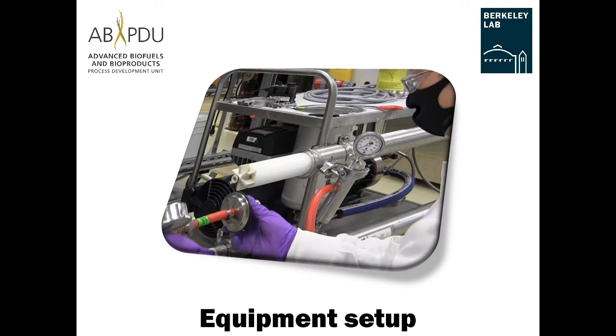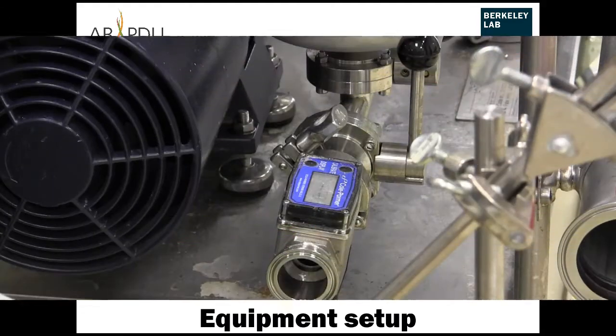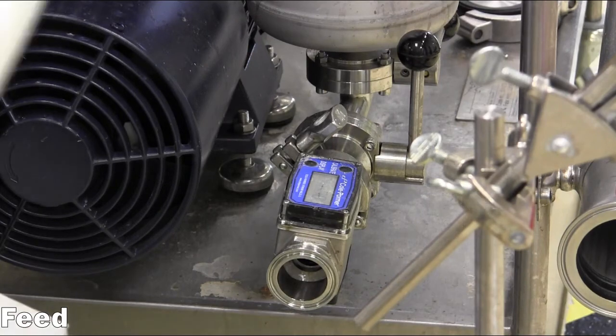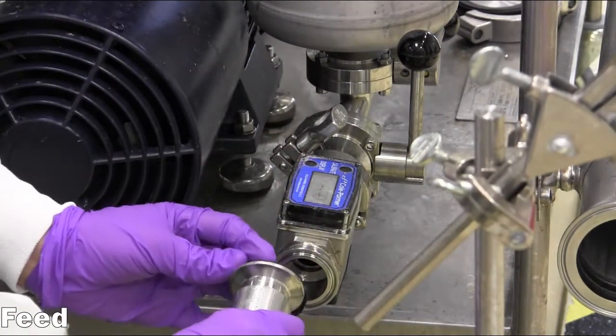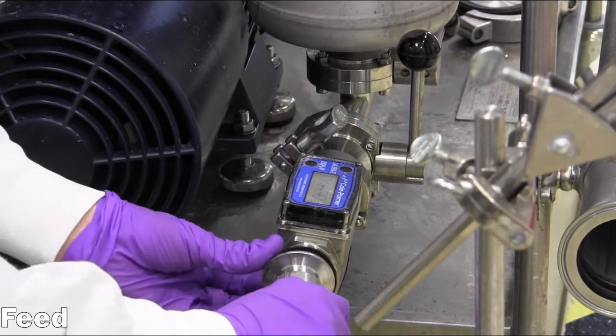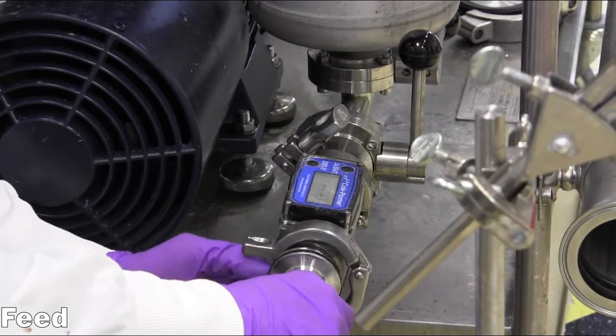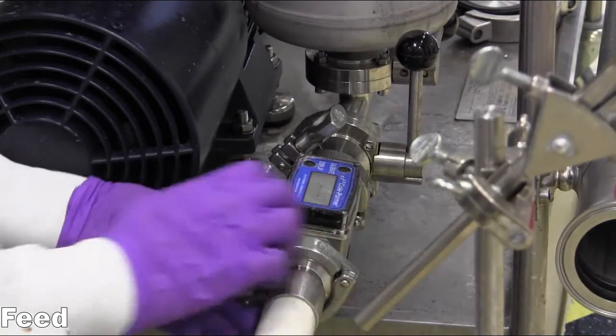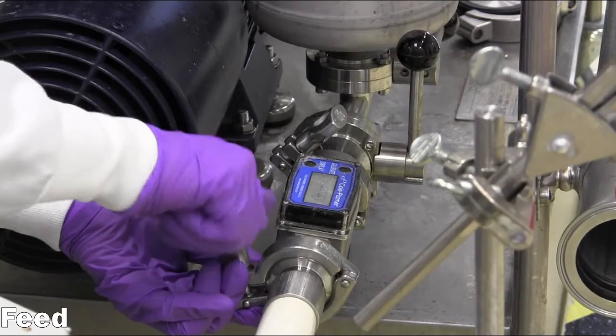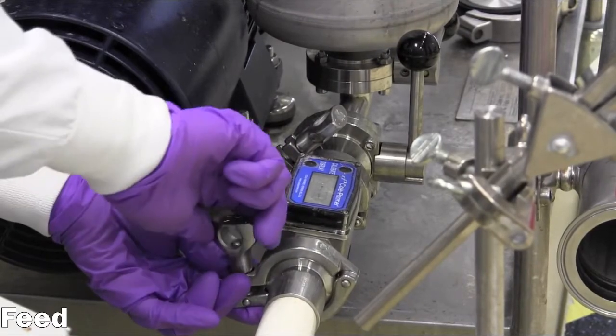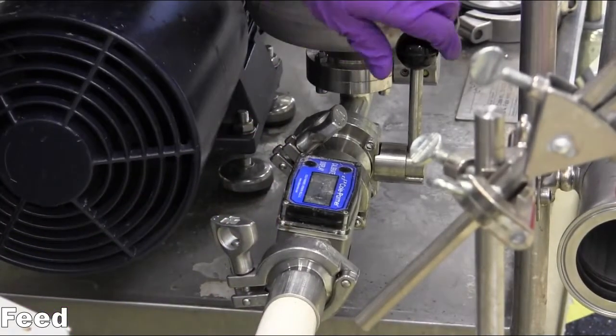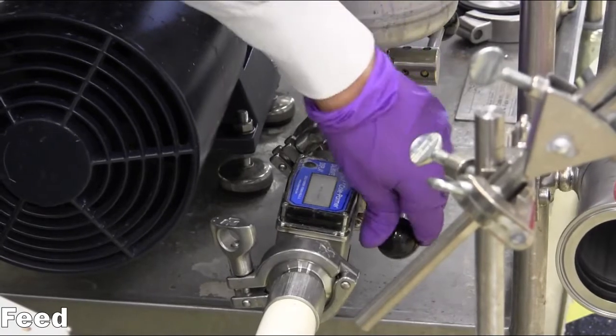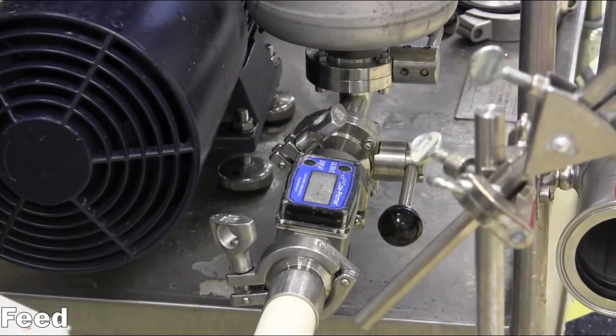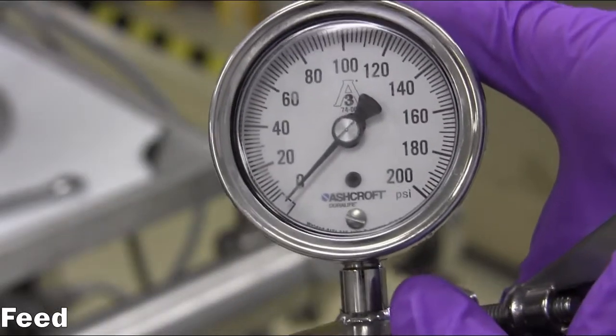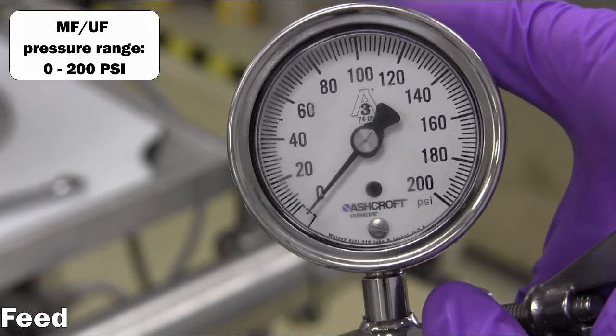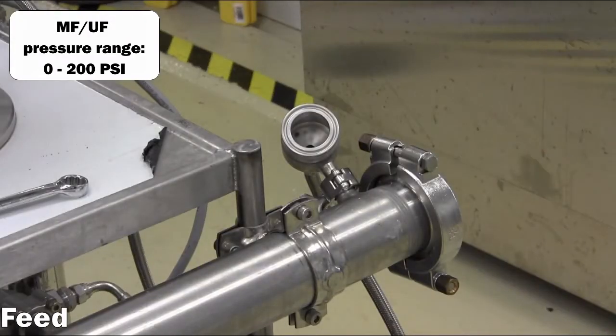Equipment setup. A hose is connected to the digital flow meter attached to the feed inlet port below the small feed tank via a sanitary tri-clamp connection. Then the three-way valve is switched to allow flow from the feed hose. Connect a pressure gauge to the inlet manifold to allow the inlet pressure to be monitored.